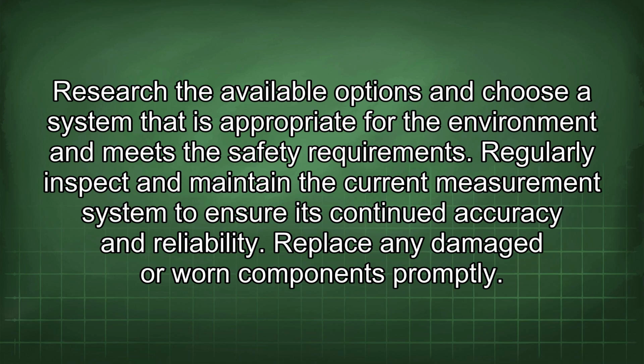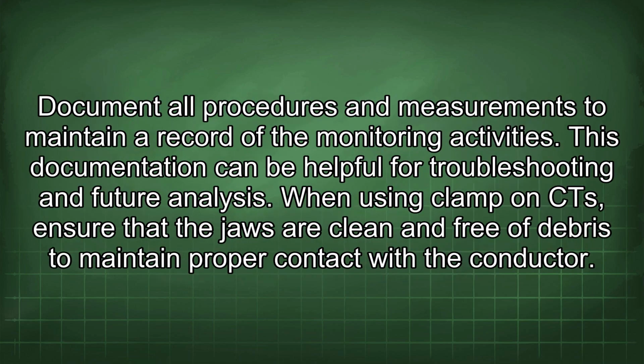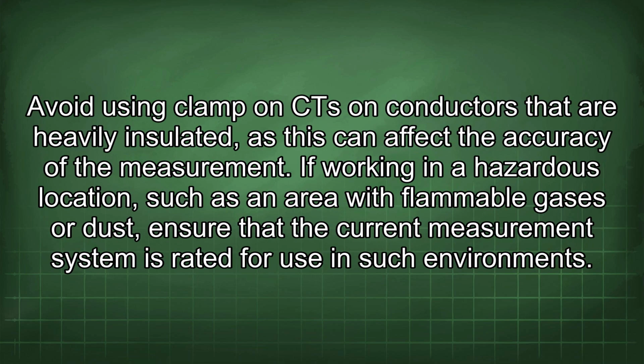Regularly inspect and maintain the current measurement system to ensure its continued accuracy and reliability. Replace any damaged or worn components promptly. Document all procedures and measurements to maintain a record of the monitoring activities. This documentation can be helpful for troubleshooting and future analysis. When using clamp-on CT, ensure that the jaws are clean and free of debris to maintain proper contact with the conductor. Avoid using clamp-on CT on conductors that are heavily insulated, as this can affect the accuracy of the measurement.